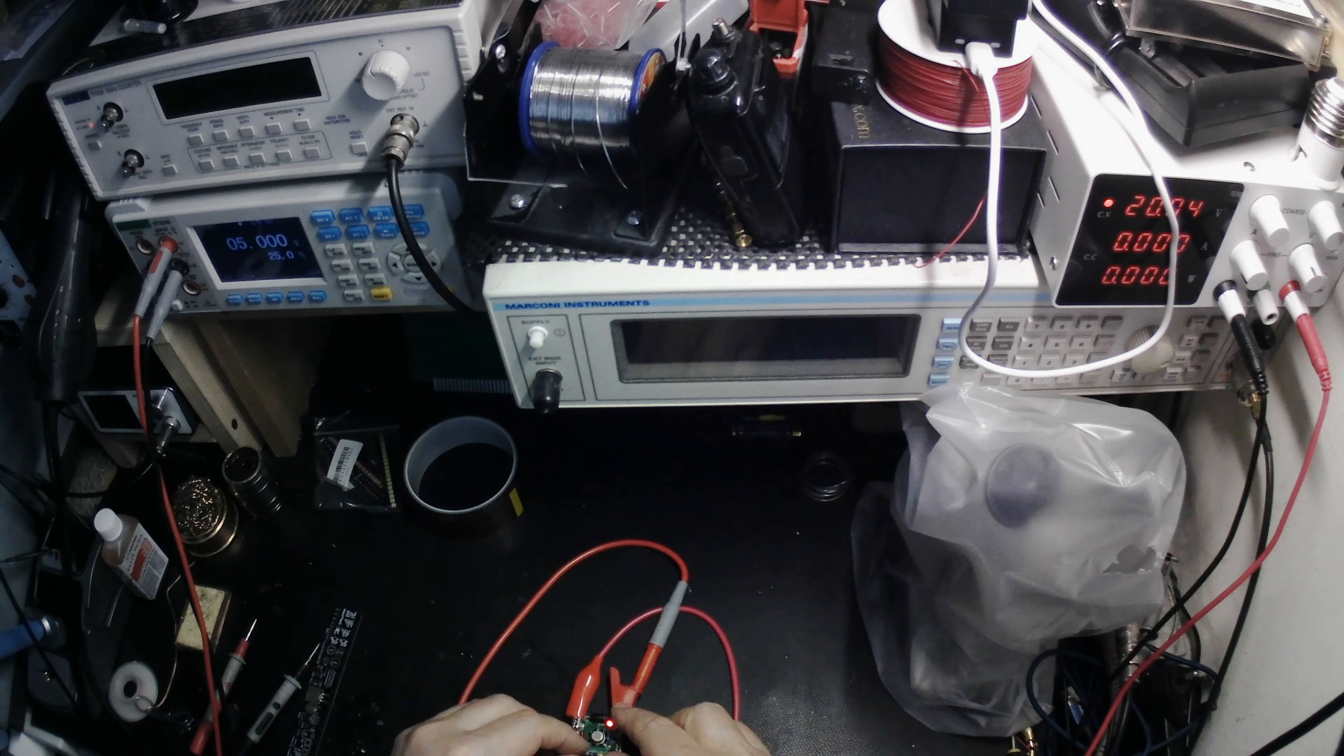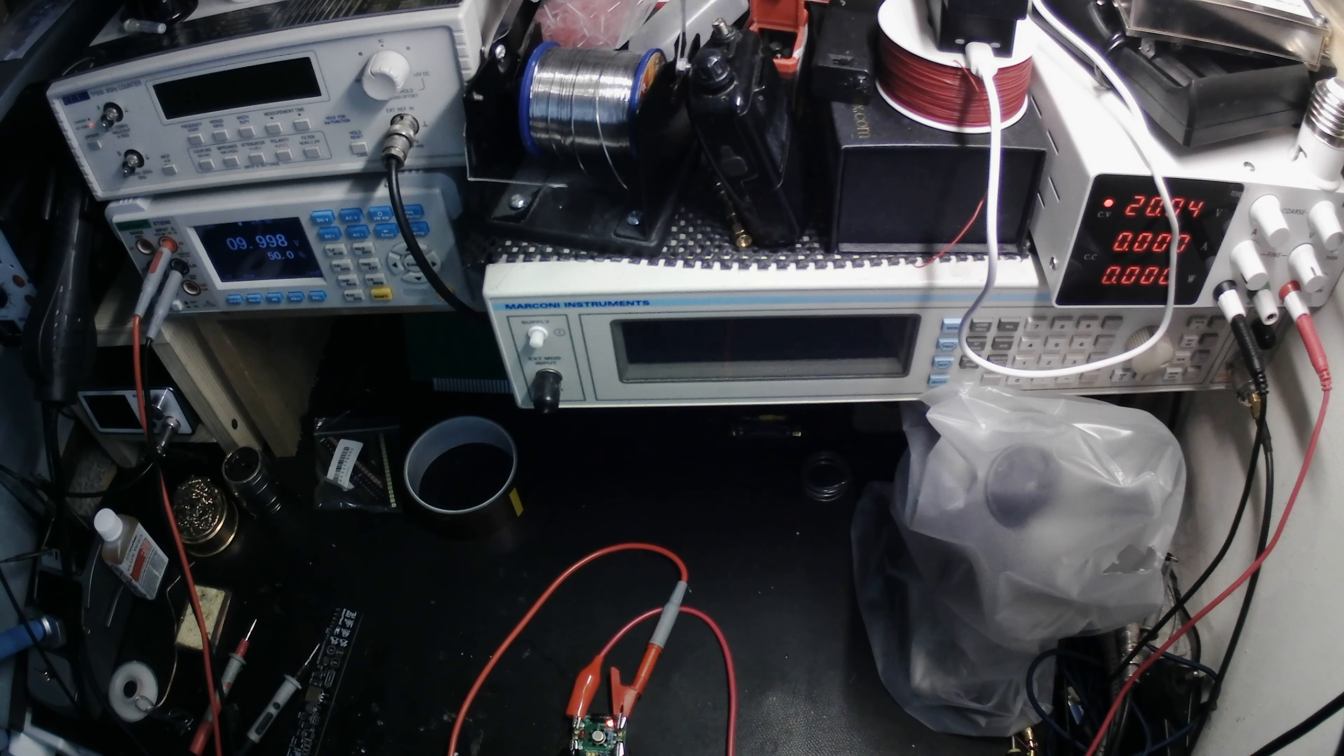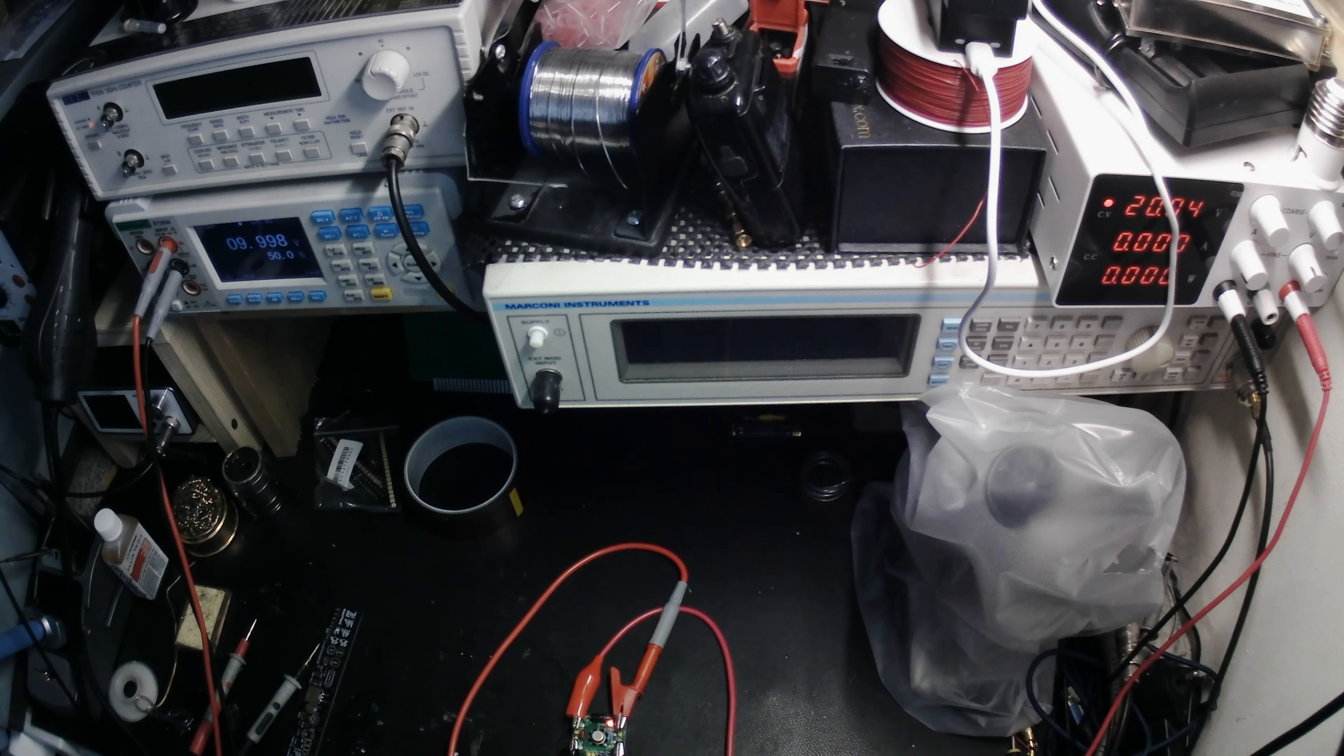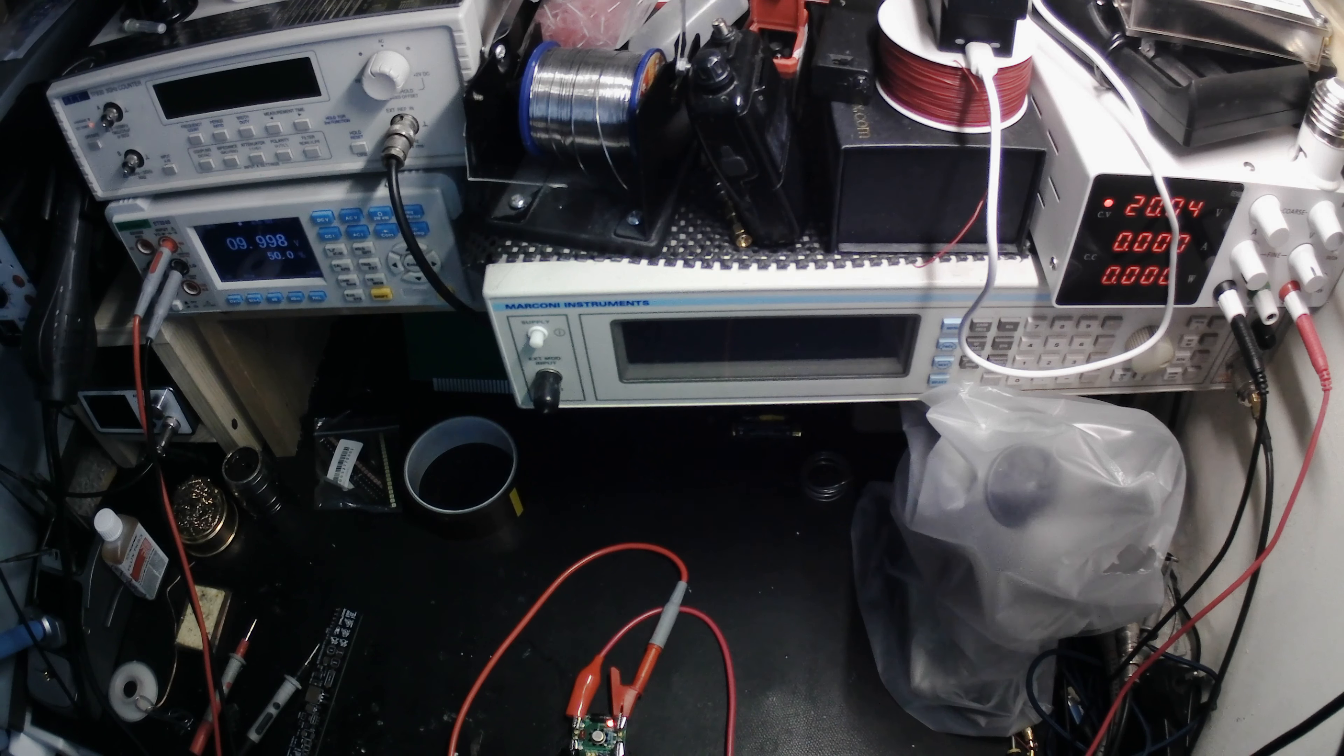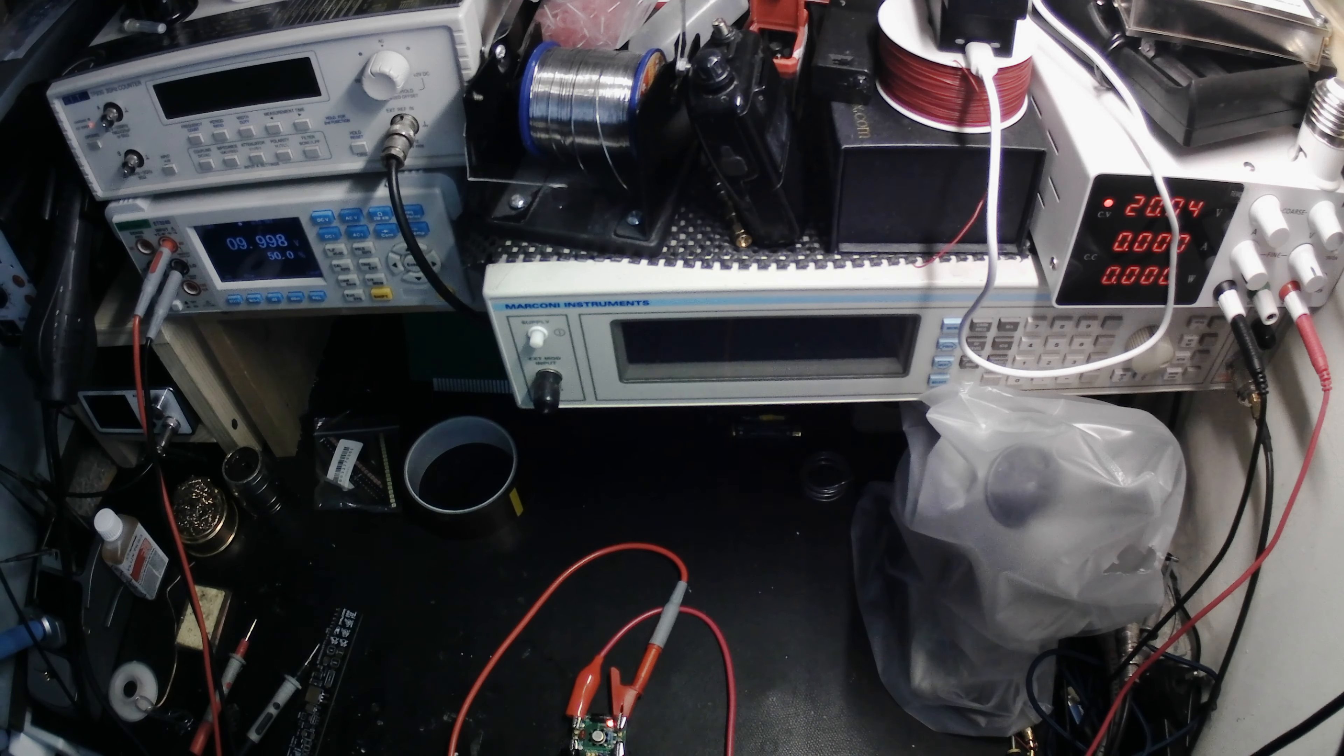So let me just turn the voltage to 10 volts and you'll see, oh that's not so good. So it's reading 9.998 volts so it's 0.002 of a volt out at 10 volts. So I might have to go back into the calibration menu at some point and just give it a tweak.